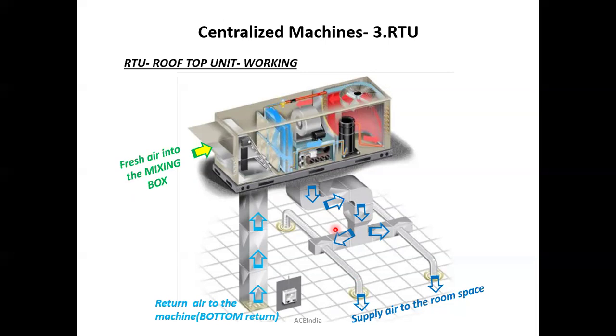All right. Is it clear? So the main advantage of this machine is a single box installation. No external connections are required. No cablings. And the other thing is that a mandatory return air duct is important, and it must be connected with the mixing box of this RTU right here itself.